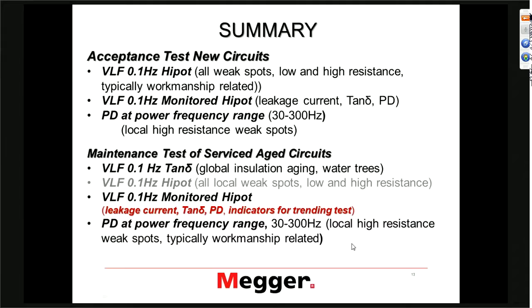When we go to maintenance testing of service-age cables, we have 0.1 Hz Tan Delta — mostly used to find the global insulation aging condition due to water trees. We have the monitored hipot test where we use leakage current. On service-age cable, it makes sense to use Tan Delta because now we're talking about the aging condition. We can also use PD as an indicator during the test, and obviously use PD at power frequency.